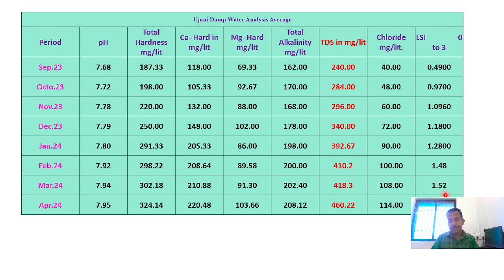Similarly, we concluded the cooling tower analysis here. From September to April, we found that the TDS level goes on increasing. That TDS level can be controlled by deliberate blowdown from the system, and deliberate or excess blowdown is also responsible for the loss of excess chemical from the system, and that ultimately increases the consumption.